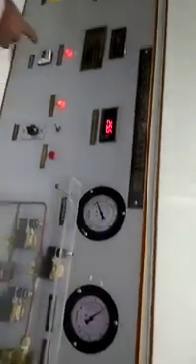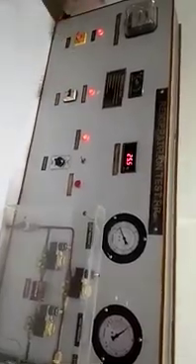And here in this setup, the capillary valve is now open. You can see the energy meter. The energy meter revolves to show how much power is supplied to run the compressor. We are going to take the readings for 5 revolutions, and the energy meter constant is 750. Because we are going to find the power required per ton of refrigeration, for that purpose we need the energy meter.